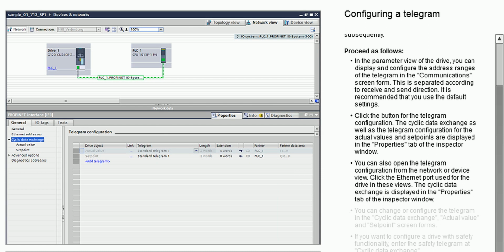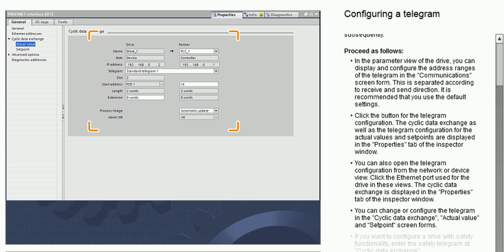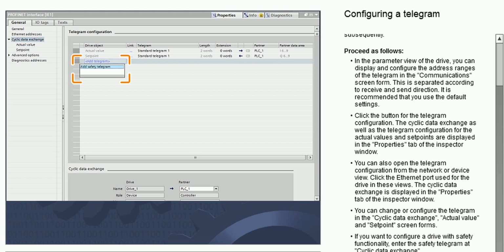You can also open the telegram configuration from the Network or Device view. Click the Ethernet port used for the drive in these views. The cyclic data exchange is displayed in the Properties tab of the Inspector window. You can change or configure the telegram in the cyclic data exchange, actual value and set point screen forms. If you want to configure a drive with safety functionality, enter the safety telegram at Cyclic Data Exchange.